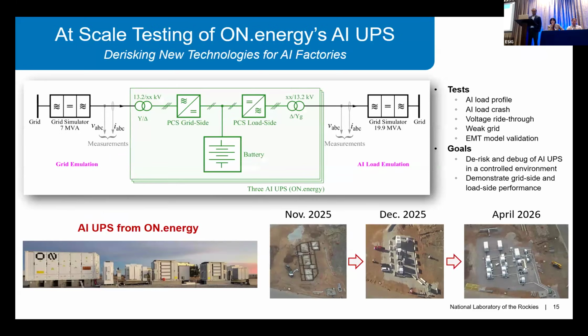So I'll conclude my presentation with this project that we have been working on with On Energy, of testing a medium voltage multi-megawatt UPS for data center applications. Instead of the low voltage UPS that are traditionally used that I talked about earlier today. This is a medium voltage UPS, sits slightly closer to grid POI, but more importantly, it uses a long duration battery energy storage, and two back-to-back inverters.